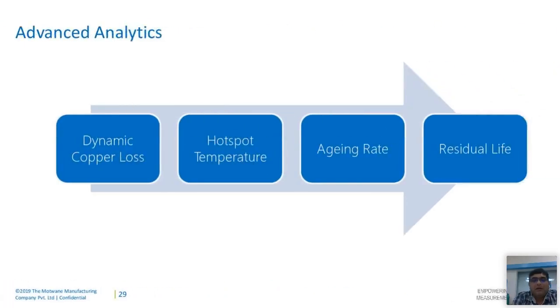Now coming to the analytics part. Typically, in the previous graph we were trending it live, but over a period of time this data helps us do a prediction of when this particular kind of event can occur. Since the operation of a transformer happens at different loading conditions, it's highly dynamic. So the data over a large period allows us to see at which particular loading percentage and at what ambient conditions this value is changing, and at what rate.